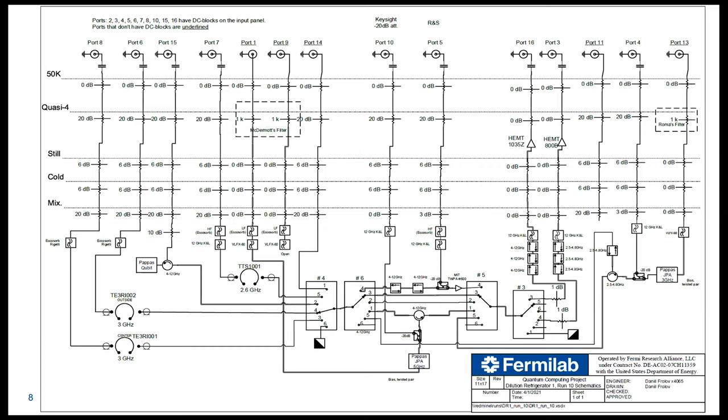This depends actually on what type of noise we are talking about. So if we talk about magnetic noise, then yes, we have to shield the fridge with an external shield. I have shown you the magnetic shielding for one qubit. What we also do is have an external shielding around the fridge made from mu metal, and so we protect it from the Earth's magnetic field. We have magnetometers inside that constantly monitor this field. We use qubits as well to measure the magnetic field down to single flux quanta levels, but we also use commercial magnetometers as a reference.